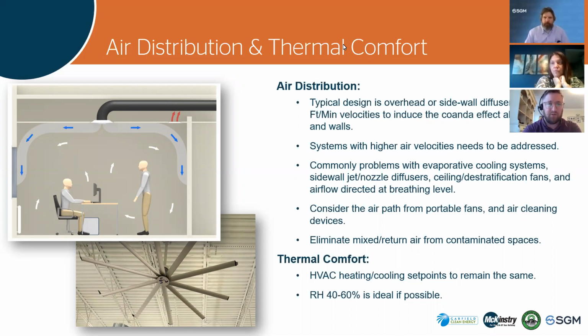So I figured I'd throw this little picture here. On the left, you can see our typical design strategy in offices and classrooms, which is overhead distribution. We're targeting about 500 feet per minute of air velocity, and we're trying to induce the Coanda effect. That effect is essentially air sticking to the ceiling and to the walls and then circulating in the space to induce mixing. So you're not blowing air directly on occupants. It's a lower velocity distribution method targeting mixing. And you can see in this picture targeting glazing at the building edge.